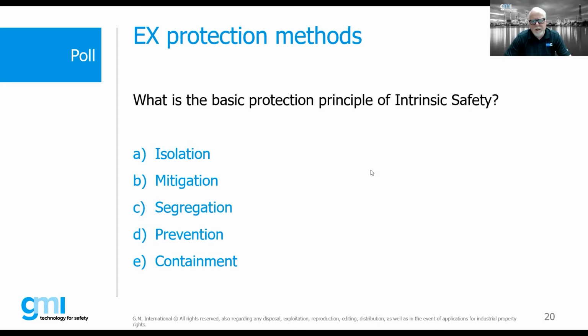Generally speaking, intrinsically safe is a great protection concept for dust because it limits the amount of energy, and we never get to levels where we're really concerned about igniting the dust surrounding intrinsically safe equipment.